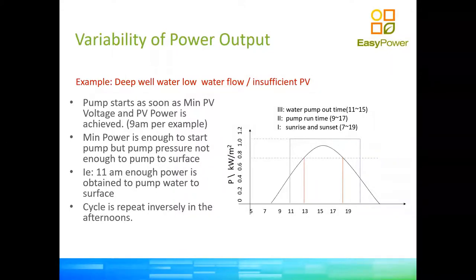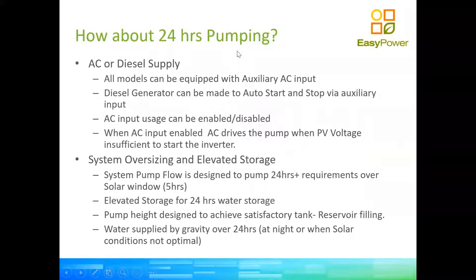To run for 24 hours, you can use the VSD and use your dam or tanks — pumping enough water during the day up to a reservoir or elevated tanks, and then at night using gravity feed for drip irrigation or normal irrigation. For high-pressure booster irrigation, you'll need an AC or battery backup to give that booster pressure. But the majority of users just use tanks and dams, do drip irrigation at night, and pump directly from the VSD during the day.